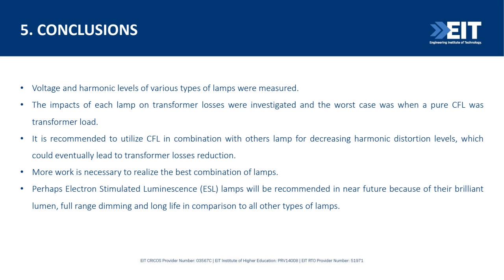How do we consider the effects of harmonics on transformers in such cases? Again, the models we have for CFLs, LEDs, and various types of lamps are inaccurate. So the best practice would be measuring the current and voltage of these lamps when they appear in the market, then simulating those harmonics and using the standard formulae to see how they affect transformer efficiency. Even for cables, there are some standards for calculating the effect of different lamps and harmonic levels on the cables and their capability.